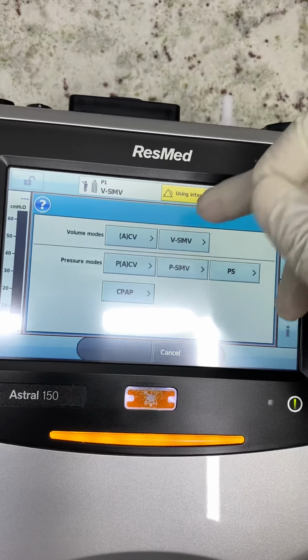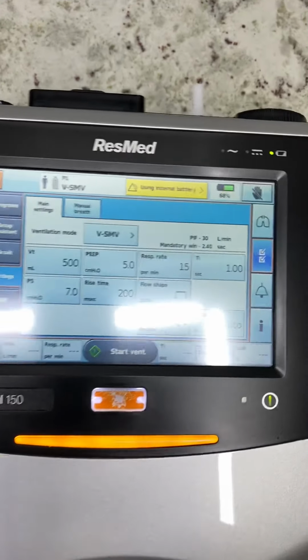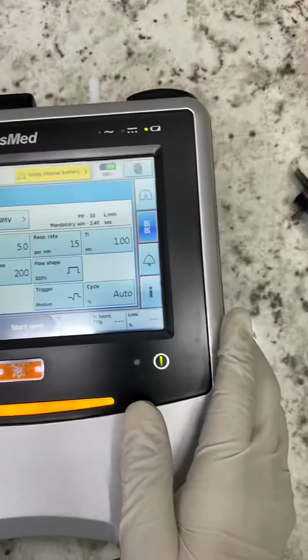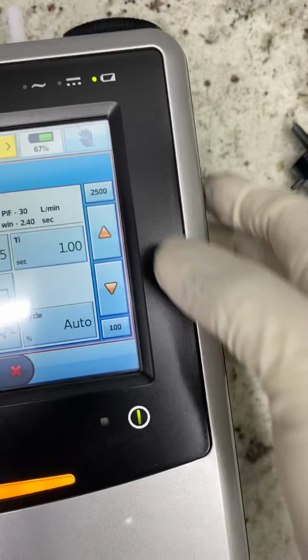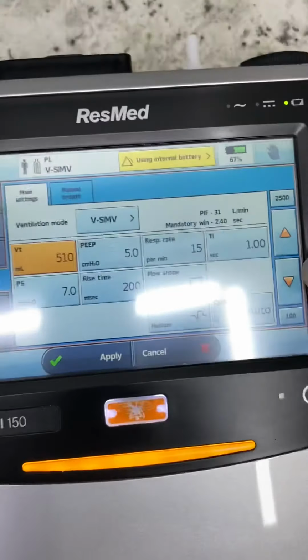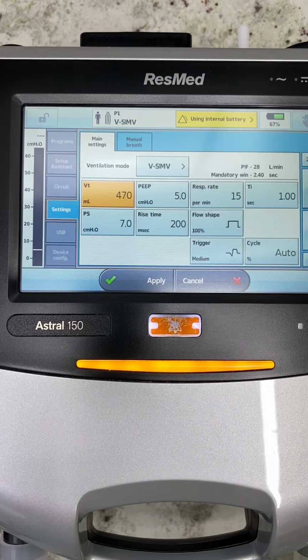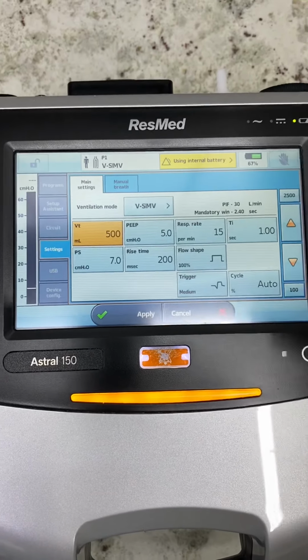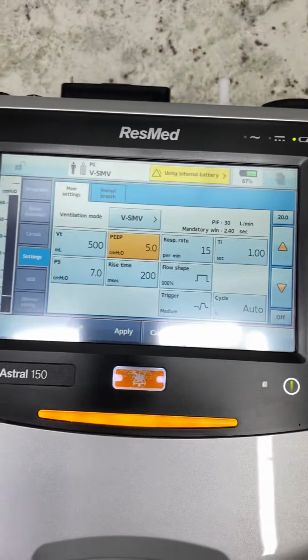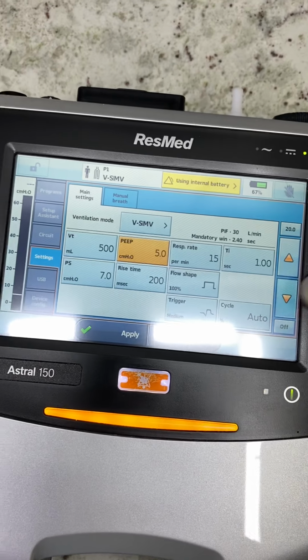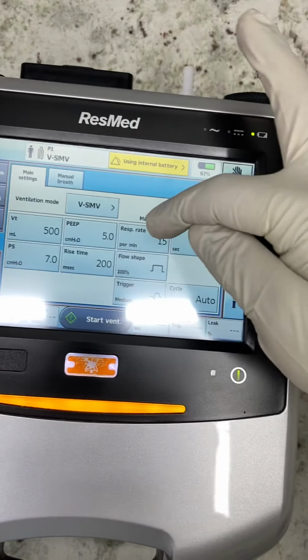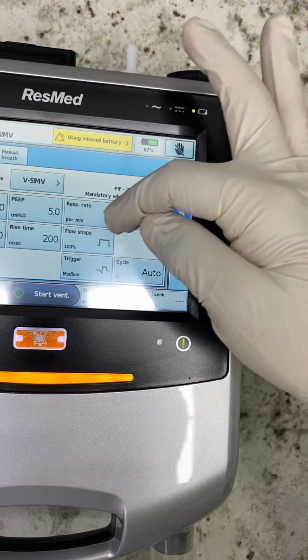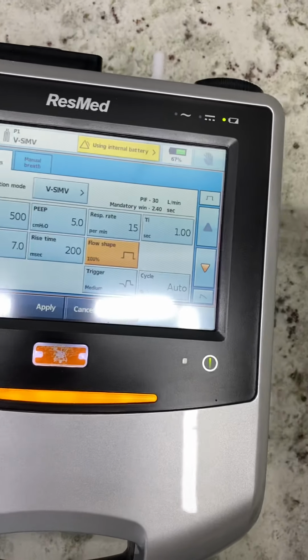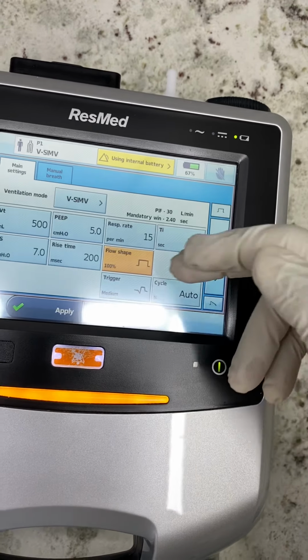Then once you choose any mode, suppose volume SIMV, choose the volume SIMV, it will come to the settings. So how to do the setting is the tidal volume. You can just choose the tidal volume. If you choose it, you can use this right hand side up or down button. See, if you choose it, the tidal volume is changing 480, 490. Once you have selected whatever parameter you wanted, you have to apply that one. So each of the parameters, like PEEP, you have to select it, press it up or press it down, then apply. Then you can see the respiratory rate, inspiratory time, flow shape. You can also choose the flow pattern. Different patterns are available.